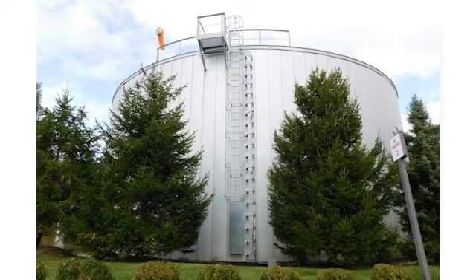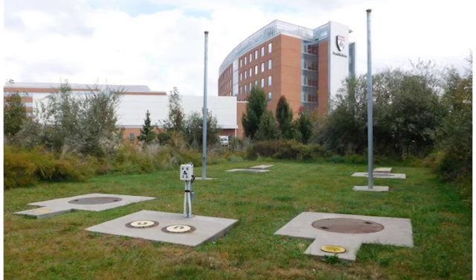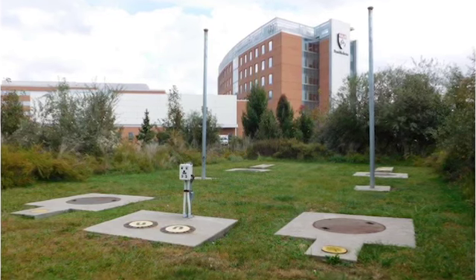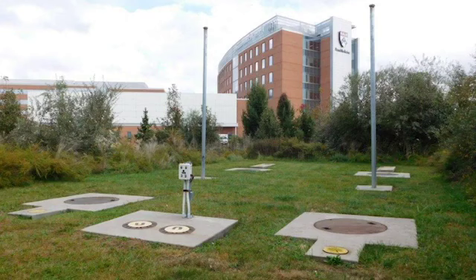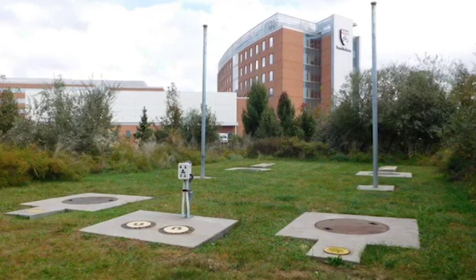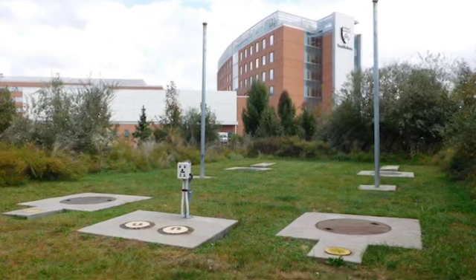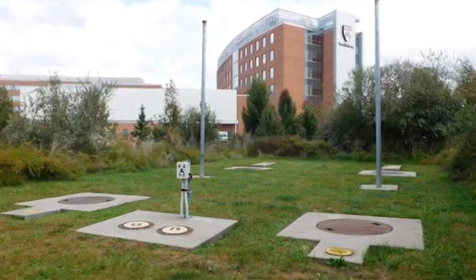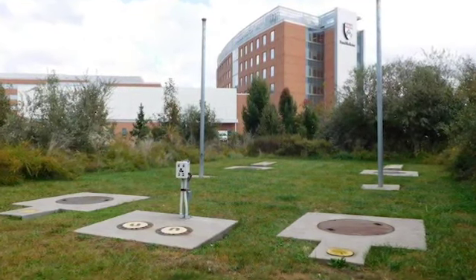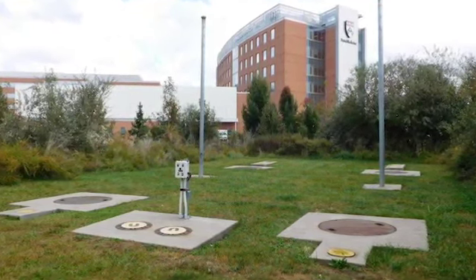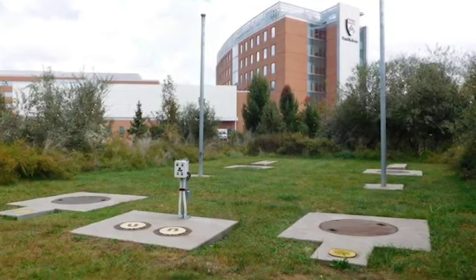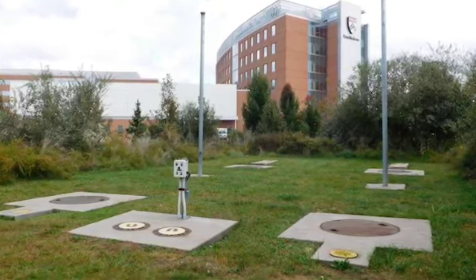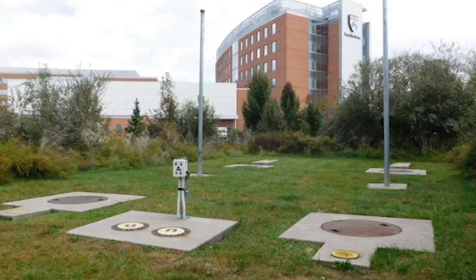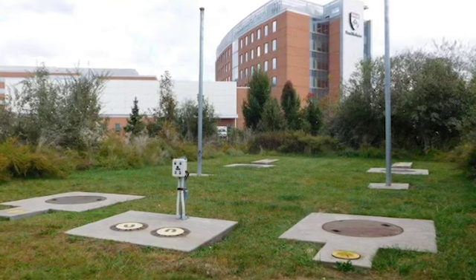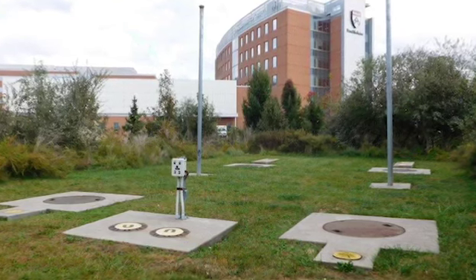Take a quick peek over at our fuel tank farm. We have 2 40,000 gallon storage tanks. We use ultra low sulfur diesel fuel. Everybody in New Jersey does. And that will take care of our diesel generators and our package boilers as well, which are dual fuel. We have about enough fuel on hand to run the hospital for 2 weeks at full emergency power load, or 1 week if we have to run the package boilers as well.